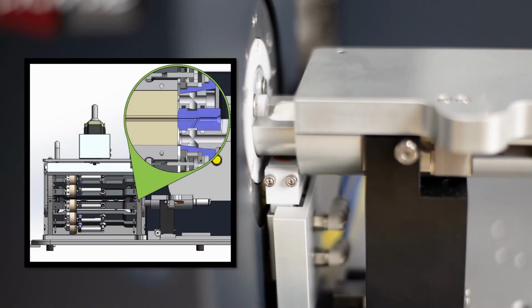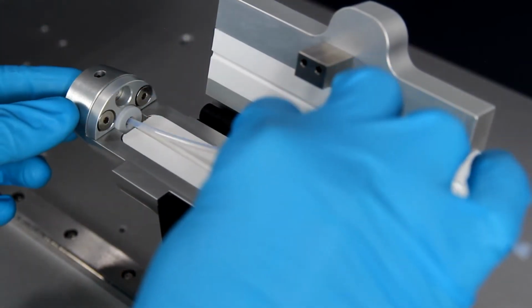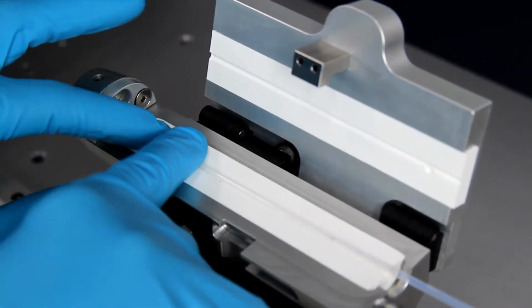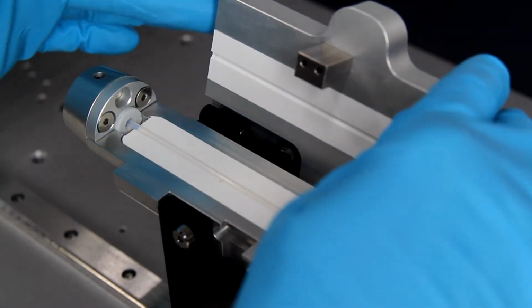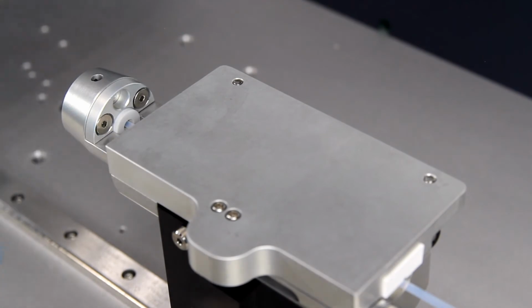The catheter should slide smoothly into the bushing, but it should not be loose, since its purpose is to hold the catheter in precise alignment with the station. It is important that the catheter and the alignment bushing are accurately placed. This will prevent a gap between the compression station and the catheter during the loading process. Next, press the catheter into the bottom channel of the silicone gripper. This channel should be a snug fit in order to prevent slippage.